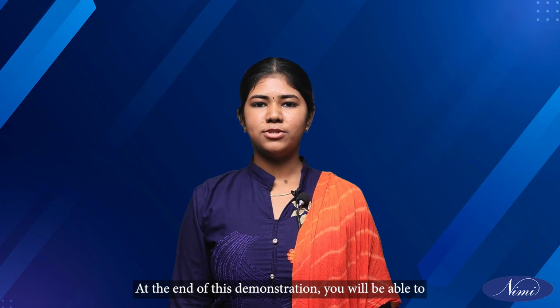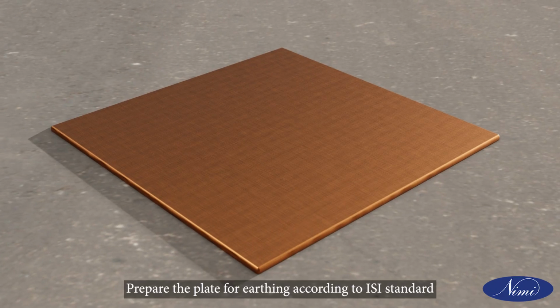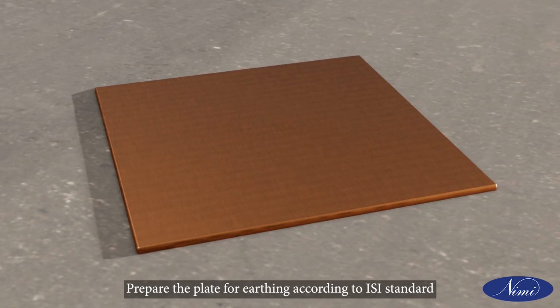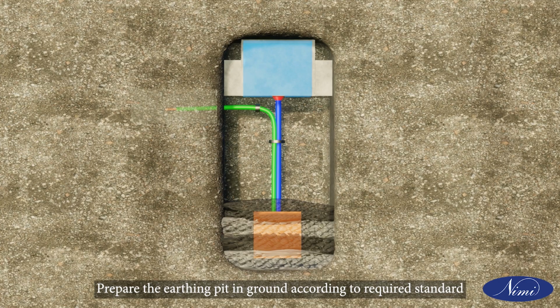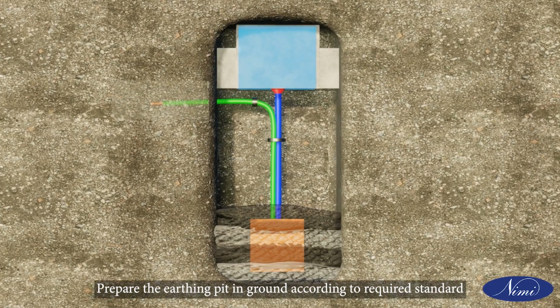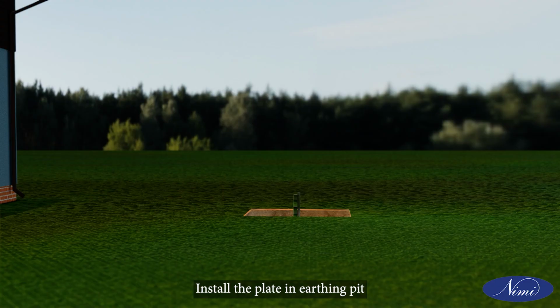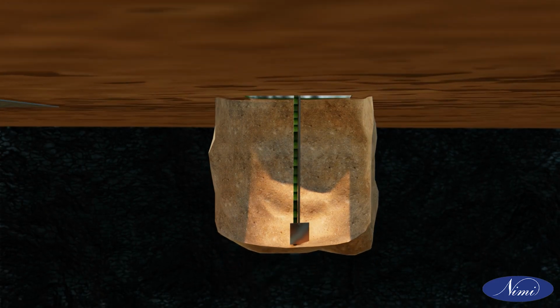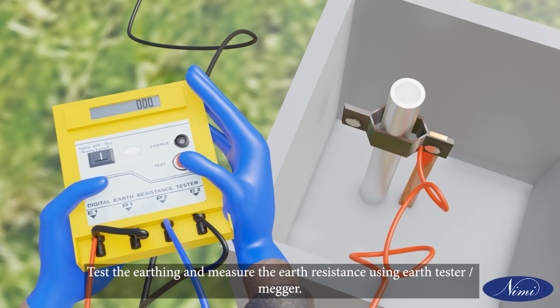At the end of this demonstration, you will be able to prepare the plate for earthing according to ISI standard. Prepare the earthing pit in ground according to required standard. Install the plate in earthing pit. Test the earthing and measure the earth resistance using earth tester or megger.